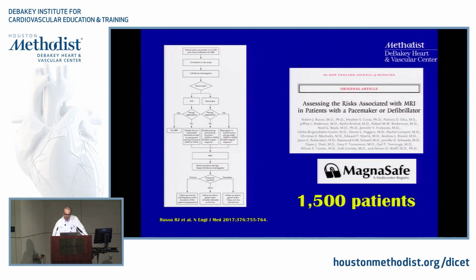So that's when there was a study, really a study of multiple folks within the MRI community with a little bit of support from the device companies, that put together a 1,500 patient study that we were involved with as well, looking at patients with non-MRI conditional pacemakers and defibrillators and asking whether these patients can be scanned safely. The key here obviously is that a very specific protocol was utilized for interrogation of the device before the procedure, reprogramming of the device for the procedure, and then follow-up of the device after the procedure was done.